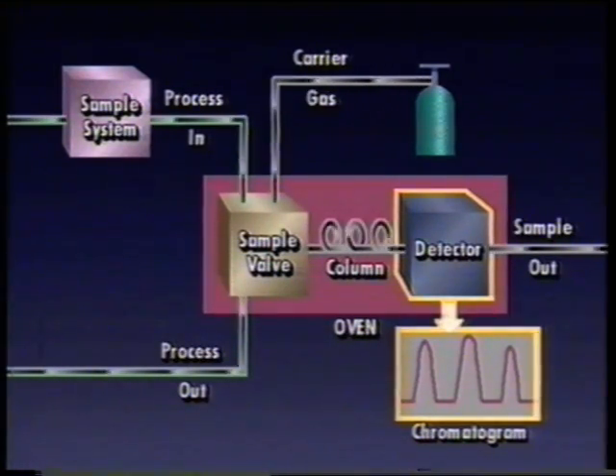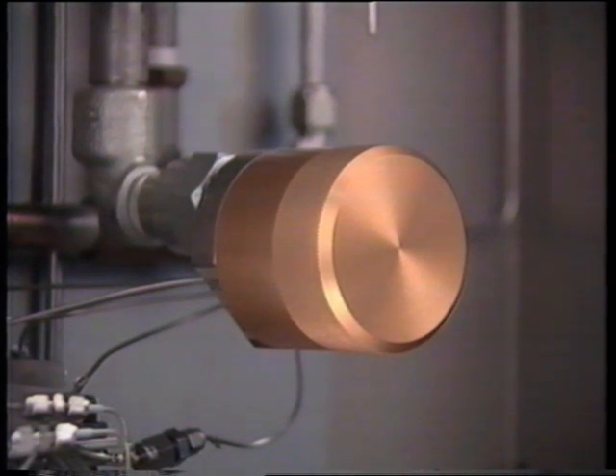In a gas chromatograph, sample components pass from the column to the detector. The detector reacts to each of the components as they exit the column. Based on this reaction, the electronics section measures and records the type and quantity of each component in the sample stream. As with other oven components, detectors are designed to operate over a wide range of temperatures and flow rates, but those factors must remain constant.